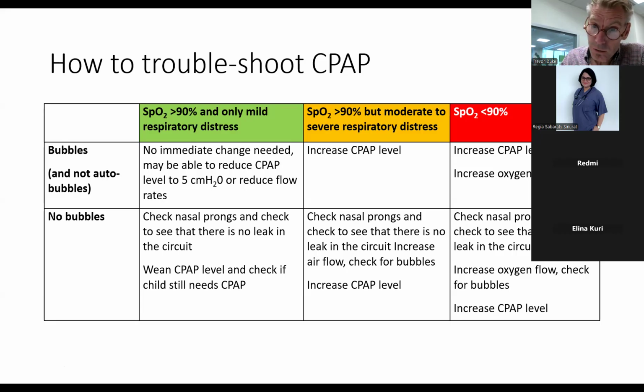Sometimes you'll need to increase the flow rate to see if you then get more bubbling, because it is dependent on the adequacy of the seal around the nostrils and also the flow rate. And sometimes you might want to increase the CPAP level to see if you can get more bubbles and the saturation to come up.